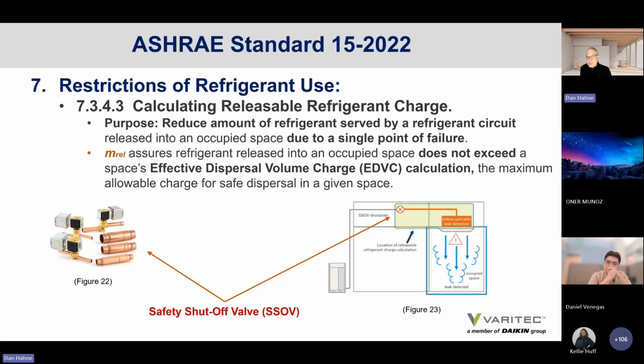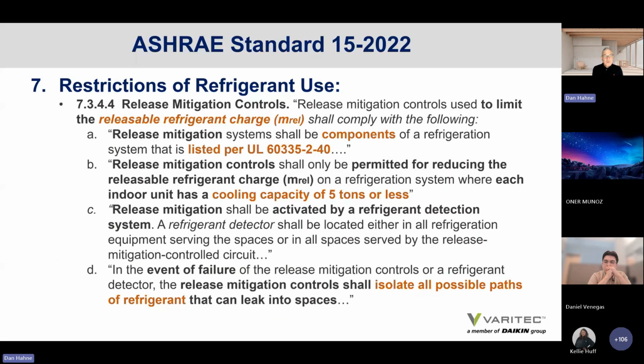And that is a substantial component of Standard 15, being able to assess whether or not a design meets the effective dispersal volume charge calculated for a space. Release mitigation controls are used to limit the releasable refrigerant charge within a space. Release mitigation systems shall have components that are UL 60335-2-40 compliant. They shall be permitted for reducing the releasable refrigerant charge on refrigeration systems where each indoor unit has a cooling capacity of 5 tons or less.